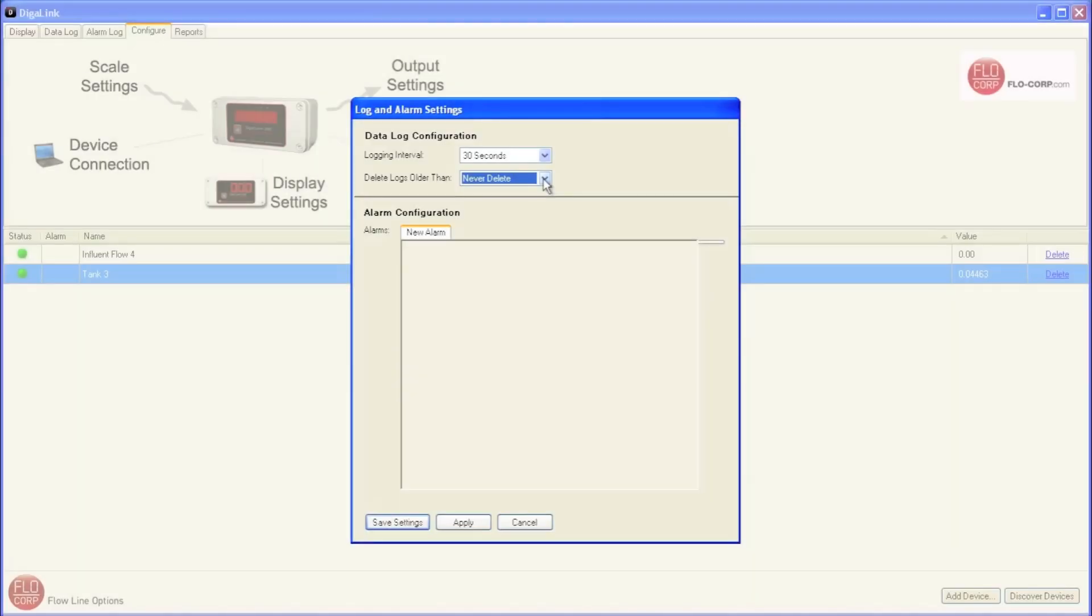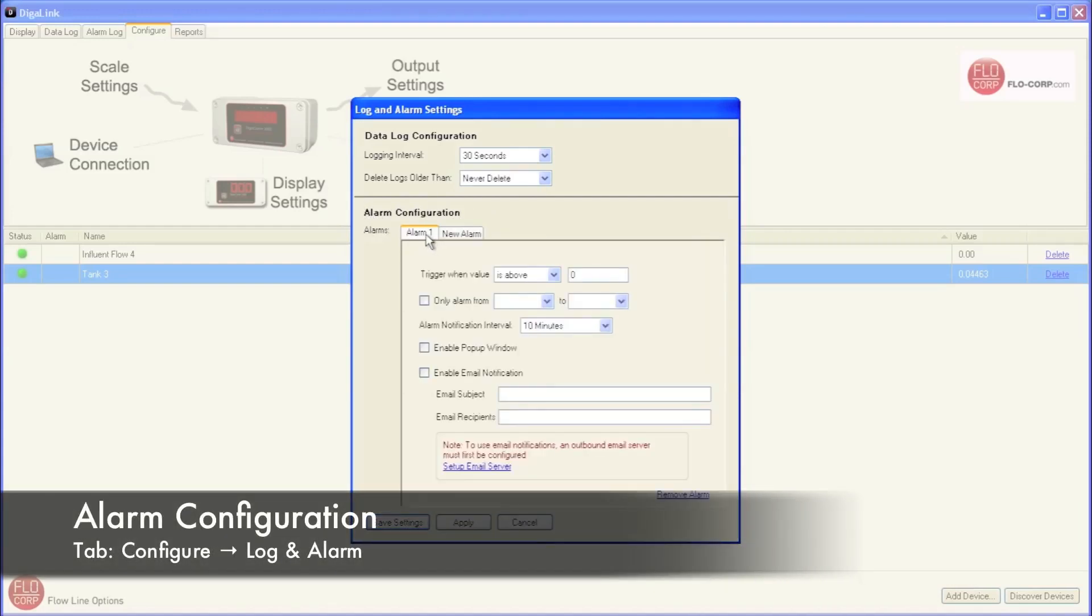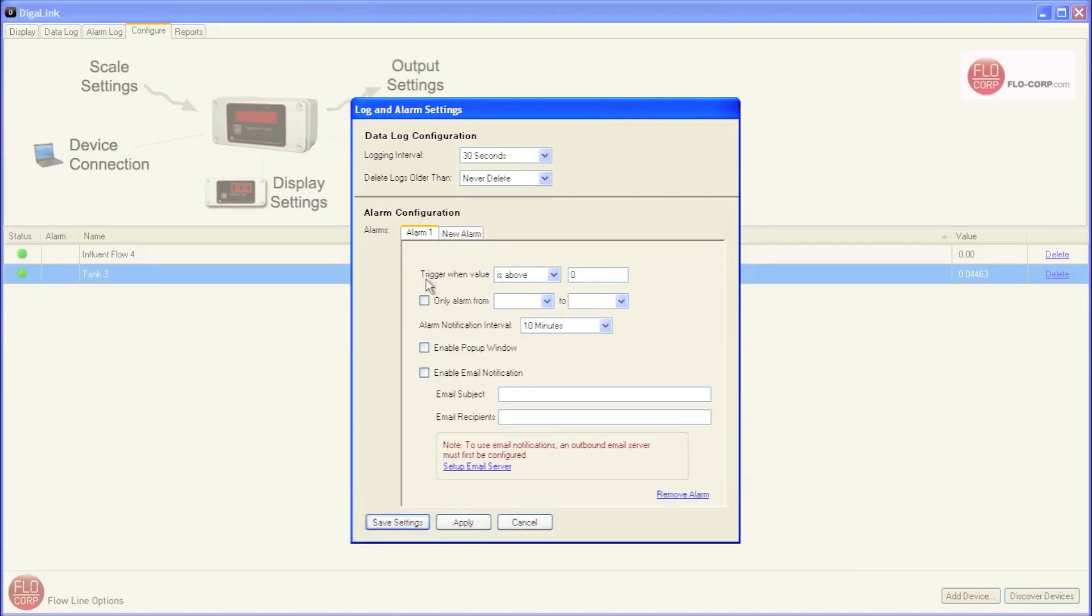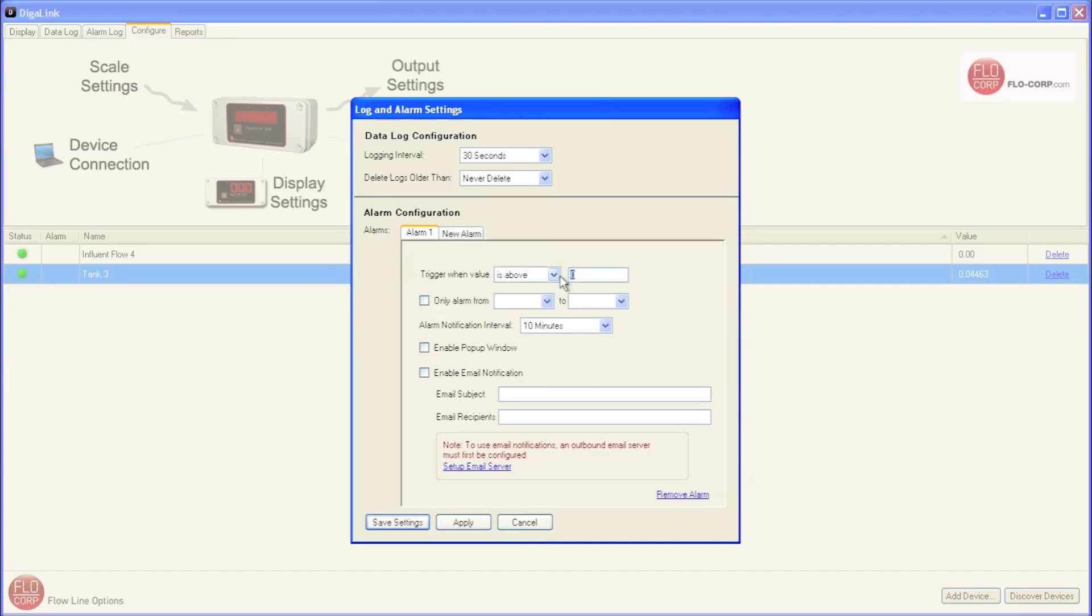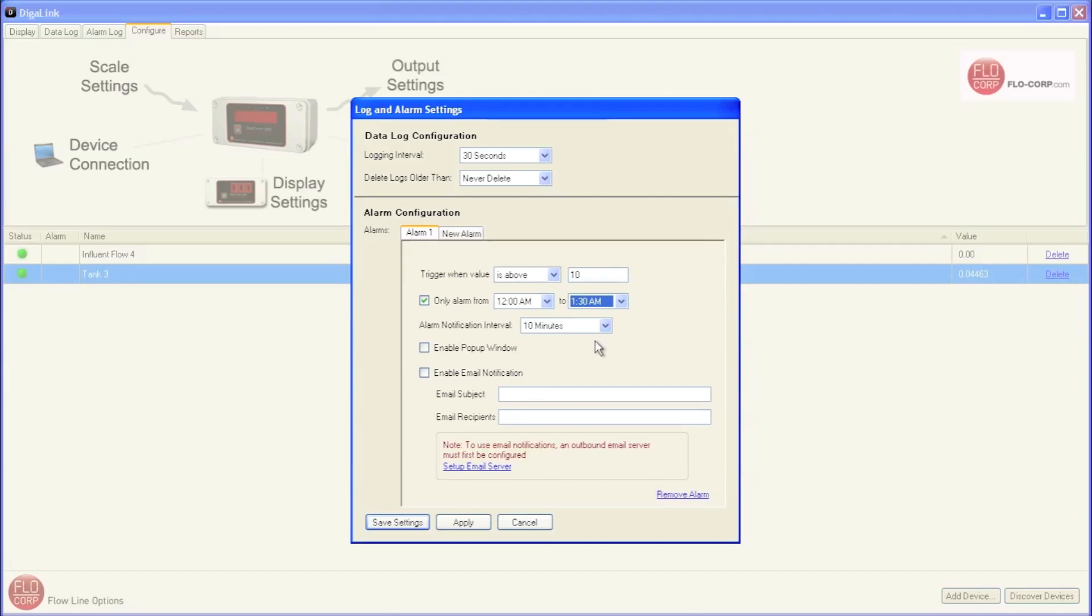The next area in the log and alarm settings window is for alarm configuration. This is where we can set up a new alarm. So I'm going to click here. Our first option is to trigger when the alarm is above, below, increases by, or decreases by. And then I can put in a value. Since our Tracer 1000 is scaled for 0 to 18 inches, I'm going to put in 10. And that will be a nice point to test our alarm. The next option is when we want the alarm to notify us. Now the device can go into alarm mode, and DigiLink will only notify us in a certain range if we use this option. So we can only be notified, let's say from 12 a.m. to 1.30 a.m. So the device goes into alarm, let's say at 10 p.m., but we won't actually get notified until 12 a.m. based on this setting. I'm going to uncheck this for the purposes of this demo.